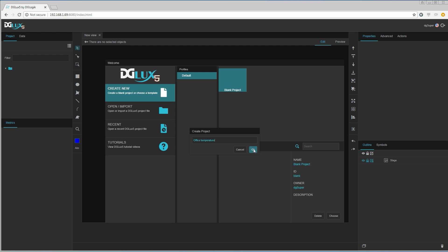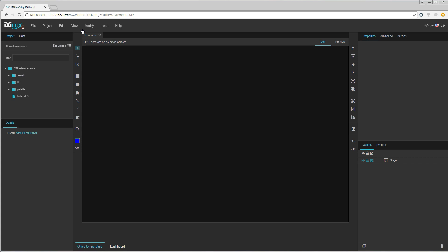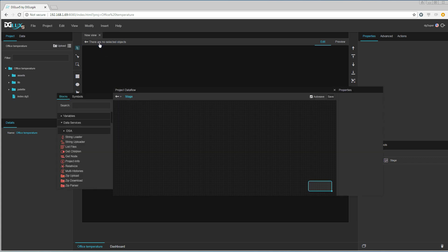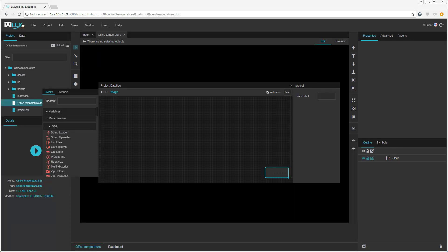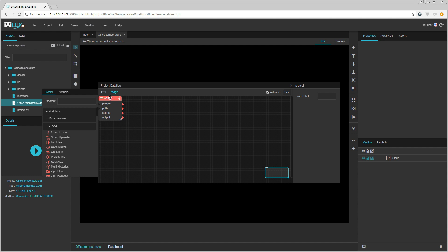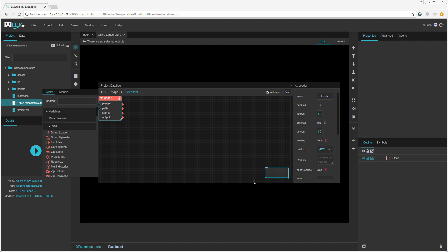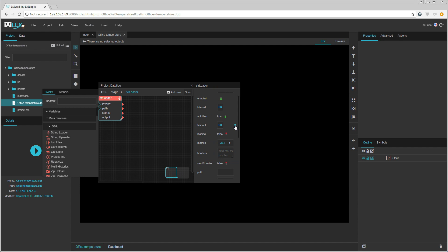Then we go to modify and choose project data flow. We are going to start by creating a string loader. The string loader is responsible for reading the data from the BACnet web services on the other Dingo device. Now we are logging the temperature values every minute on the other Dingo device, so we set the string loader to run every 60 seconds to get the newest data.